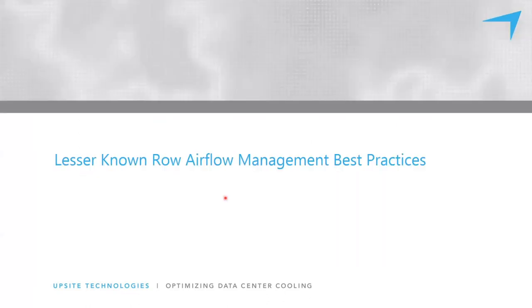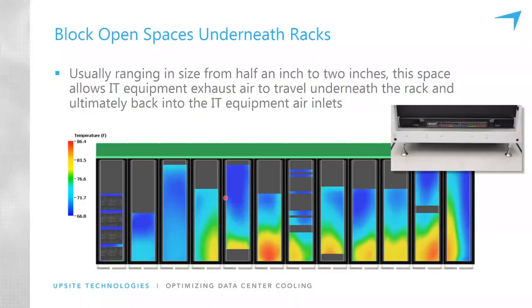So let's look at a couple of the less addressed issues in managing air at the row level. The first one is looking at spaces underneath cabinets. This image on this page and the next page are CFD analysis of a room. And it shows that the warmest intake temperatures to the face of the cabinets in the cold aisle are occurring across the bottom of the cabinets. And this is happening regardless of how much supply air is being delivered to the cold aisle.